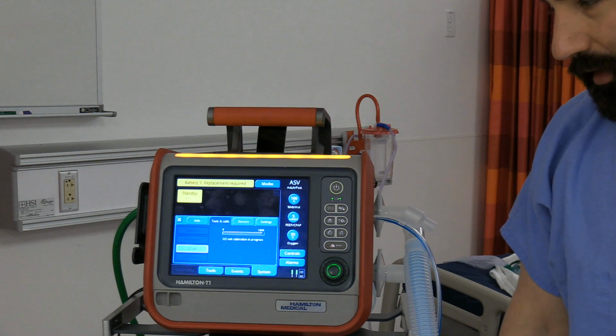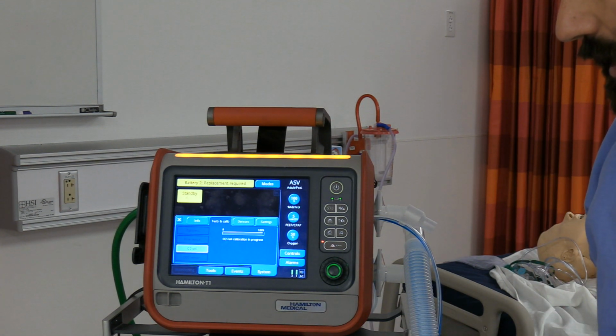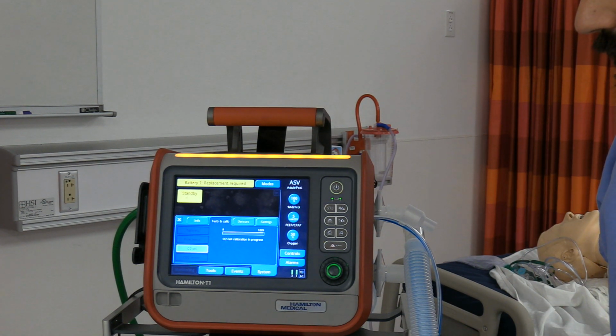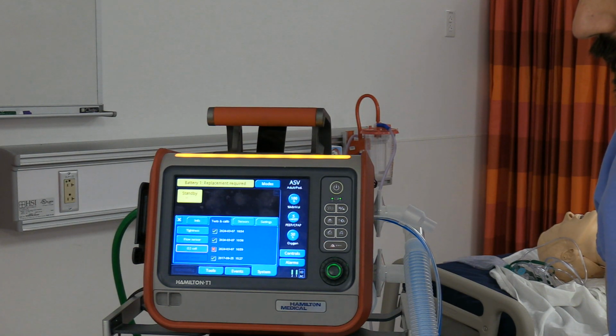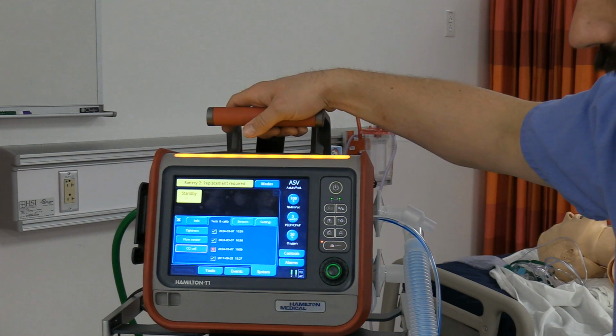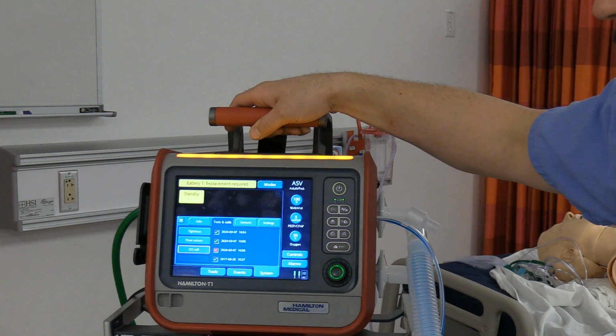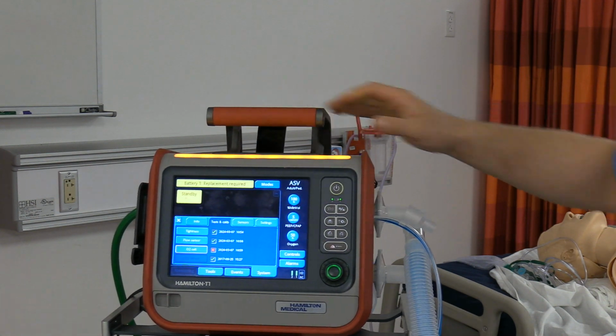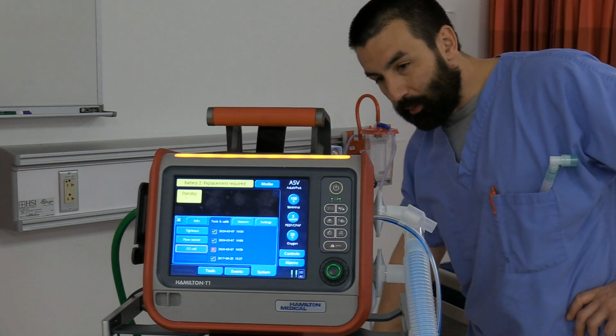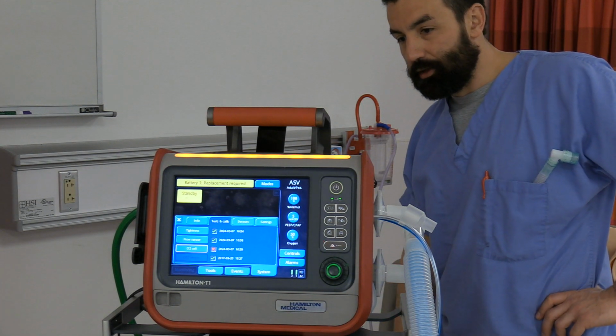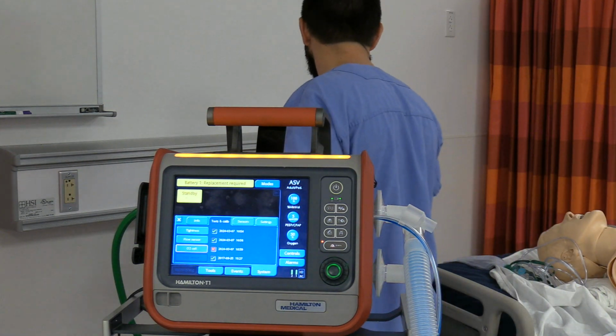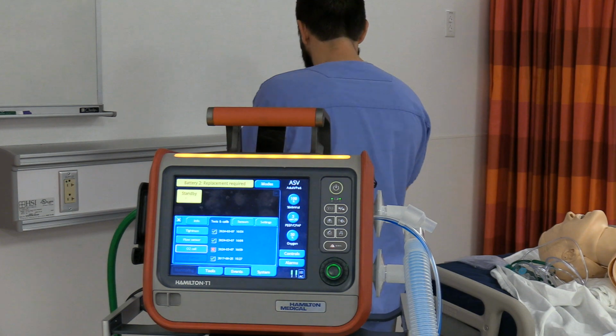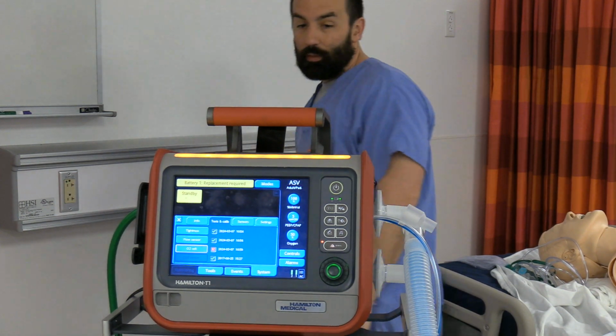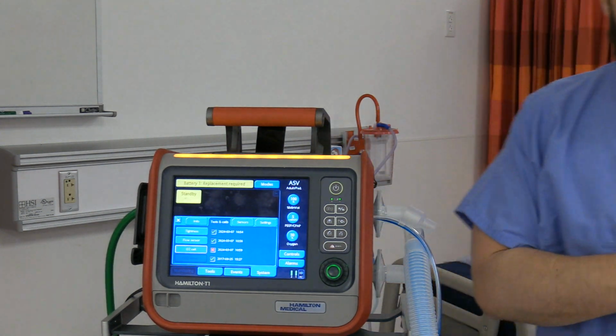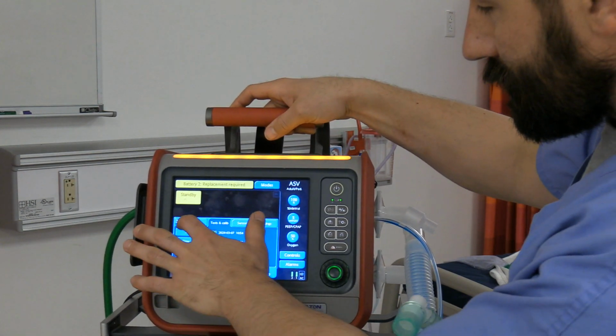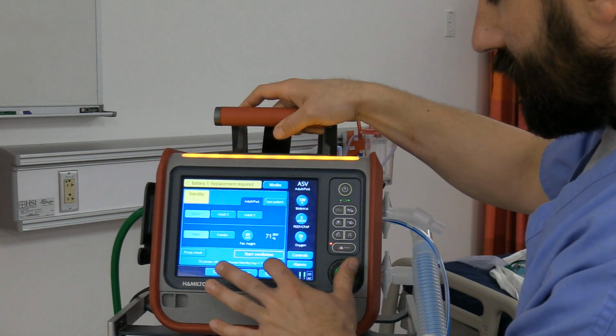Could have probably skipped this one, but it needed to be done. And it failed. It could have failed because my ventilator is overdue for preventative maintenance and maybe needs a new sensor. That is okay. It would not be okay for a regular patient, okay? We would pull this to the side. I'm going to show you a little workaround here. I'm going to click out of this.